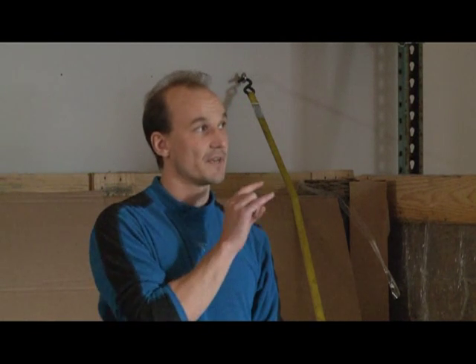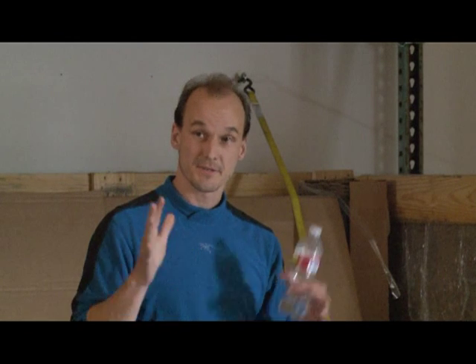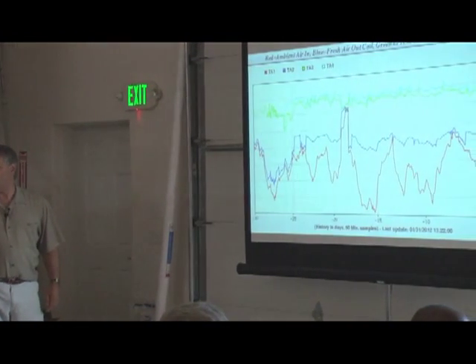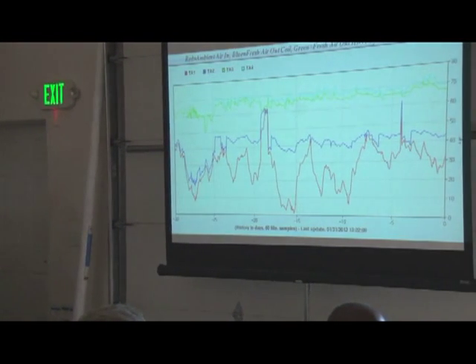Standard units still run at 72 to 80 watts just to operate. To give you an idea, that project in Vermont running a ground source unit: when the pump is running, it's running a combined 25 watts — 7 watts for the pump plus 18 for the HRV. We're looking at 25 watts monitored on a data logger. You can see it go from 18 to 25 when the pump comes on.